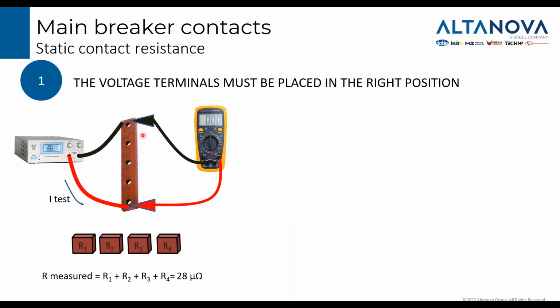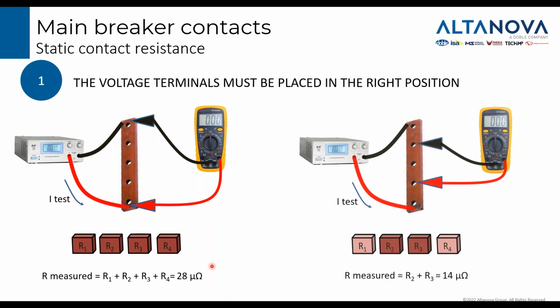If I measure the voltage in this position, for sure I am measuring the 4 elements and I get the right value, 28 microohms. But if I change the position, as in the picture, it is equivalent to measuring only 2 of the 4 elements. Then I get 14 microohms. If I look at the error in percentage, I'm making an error of 100%. You can see with this very simple demonstration how important the position is that you choose for the clamp for the voltage measurement.